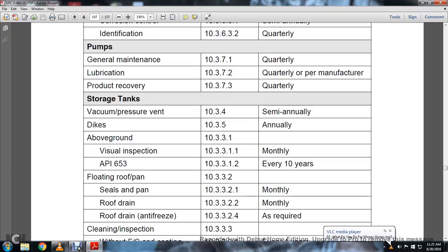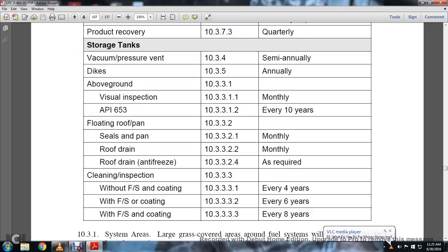Storage tanks. Floating roof pan 10.3.3.2 sections. Seals and pans 10.3.3.2.1 manual monthly. Roof and drain 10.3.3.2.2 monthly. Roof drain antifreeze 10.3.3.2.4 as required. Cleaning and inspection: without the filter separator, coating 10.3.3.3 every 4 years. With filter separator or coating, storage tank 10.3.3.3.2 every 6 years. With filter separator and coating, storage tank 10.3.3.3 every 8 years.